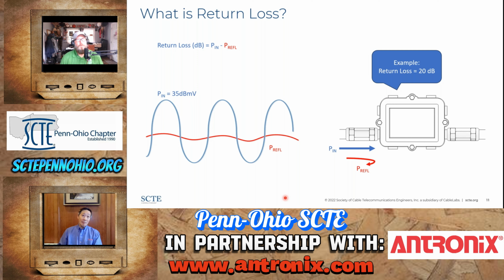So even if you have products with a spec of good return loss, there are many things that affect the return loss, like you mentioned before, impairments. A simple bad connector, squirrel chew, and these things are all normal in the network, or they're supposed to be 75 ohms. You could have unterminated ports. So if you have a device here and one port doesn't have a 75 ohm terminator connected to it, you could affect the return loss on all the other ports if one of the ports is not terminated. So those are all things that could affect return loss in the network.